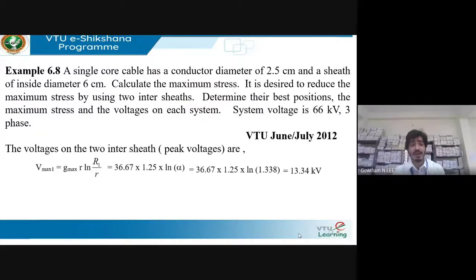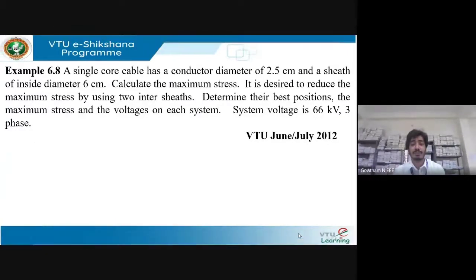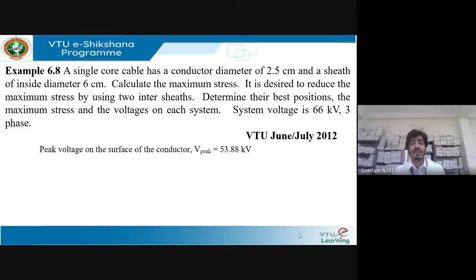V_max1 = Gmax × r × ln(R1/r) = 13.34 kV. V_max2 = Gmax × R1 × ln(R2/R1) = 17.86 kV. The peak voltage on the surface of the conductor, calculated initially, corresponds to 53.88 kV.